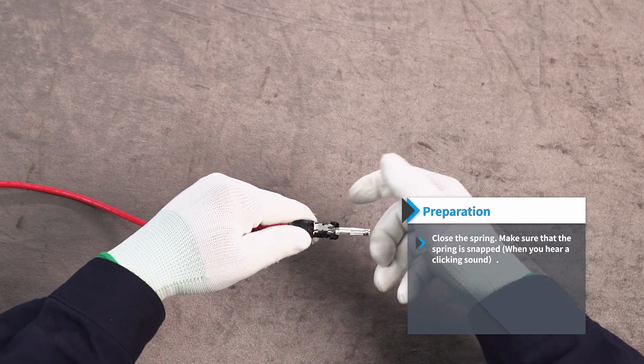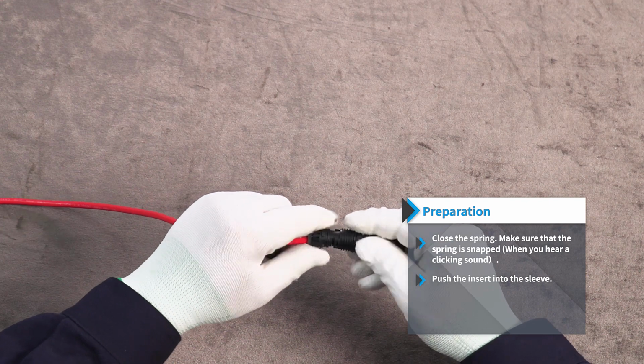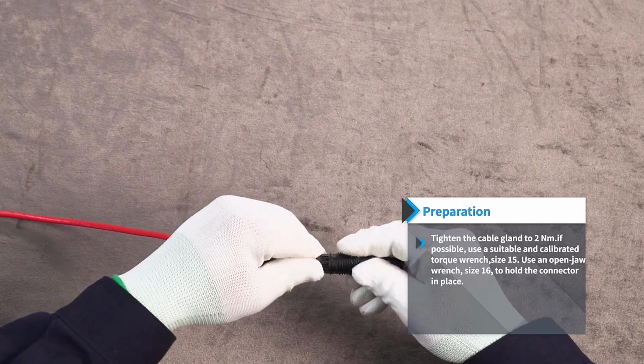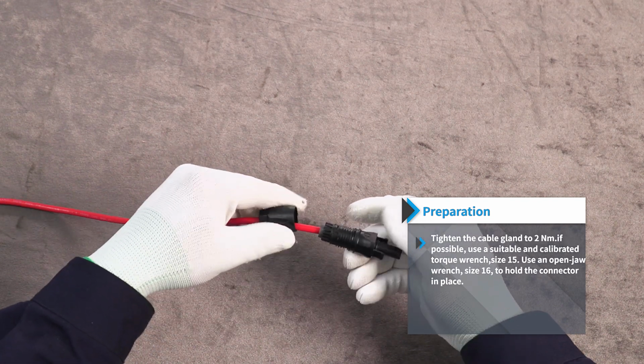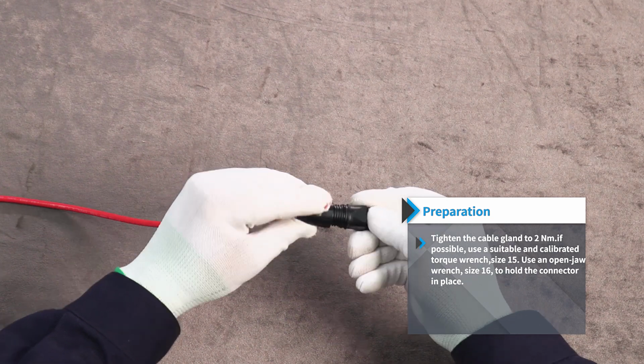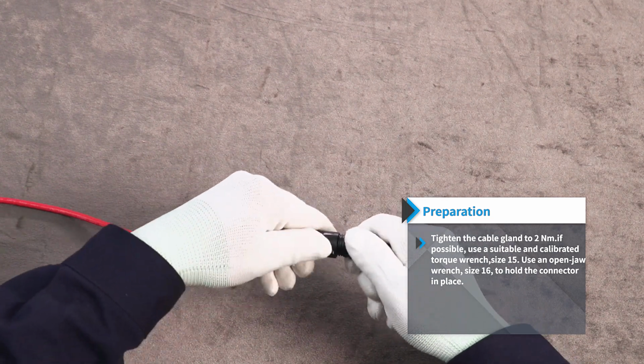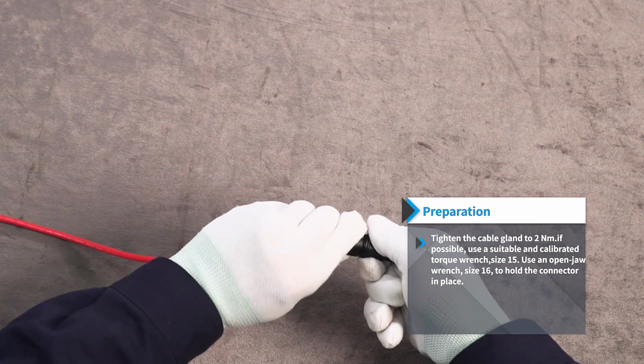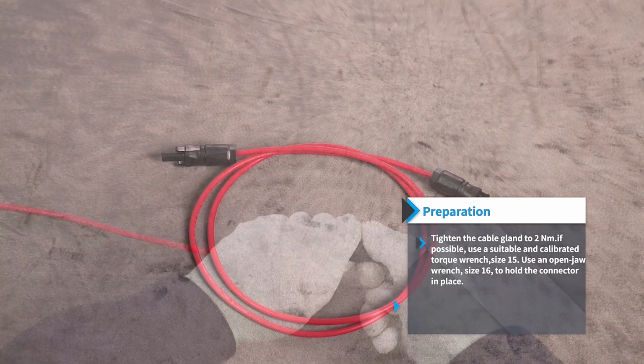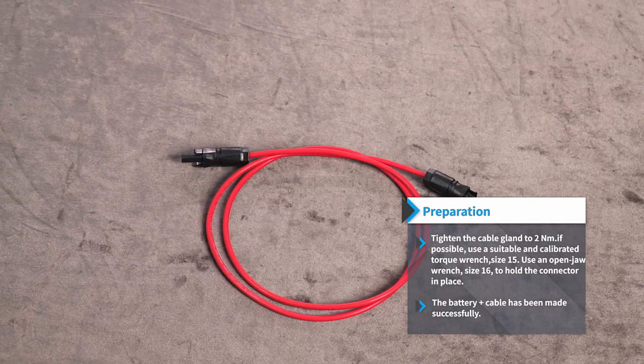When you hear a clicking sound, push the insert into the sleeve. Tighten the cable gland to 2 Nm. If possible, use a suitable and calibrated torque wrench, size 15. Use an open jaw wrench, size 16, to hold the connector in place. The battery positive cable has been made successfully.